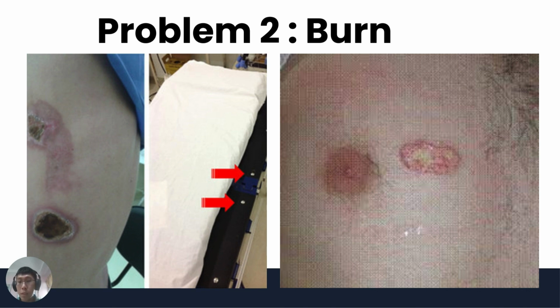In the past, these units included a continuity monitor which prevented ESU activation in case of a break or disconnection in the return electrode cable from either the ESU or the electrode. However, this type of monitor couldn't detect partial or complete detachment of the return electrode from the patient, potentially leading to patient burns.